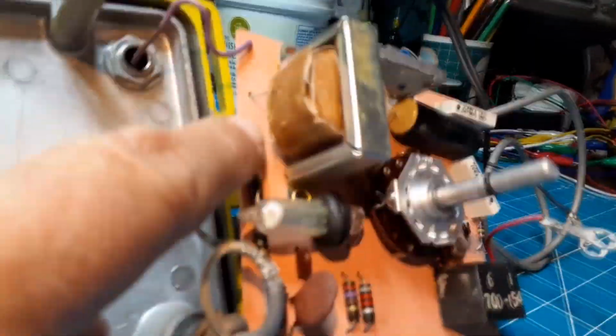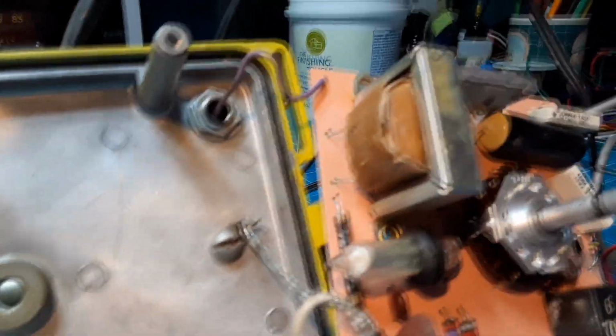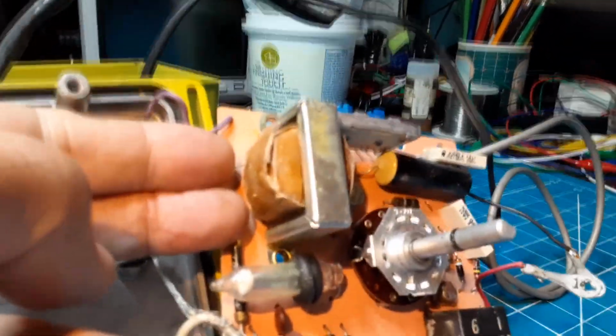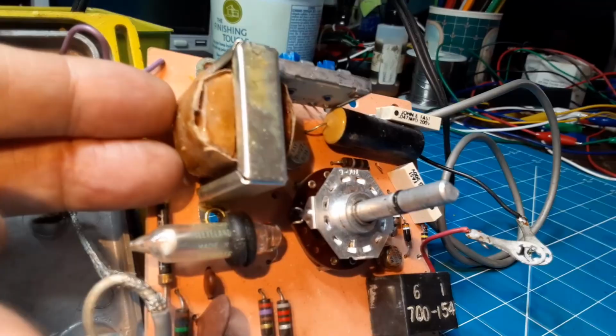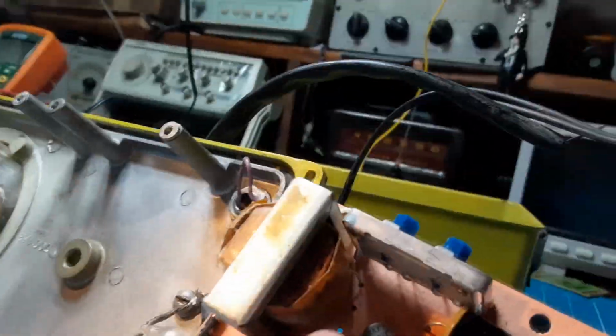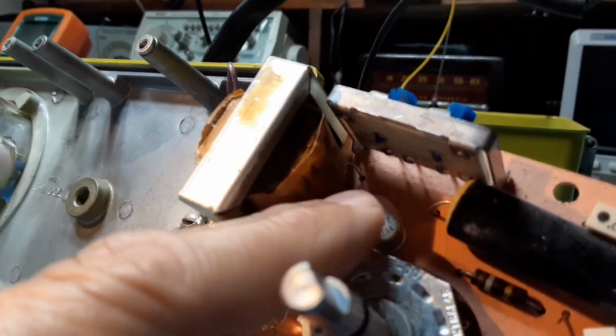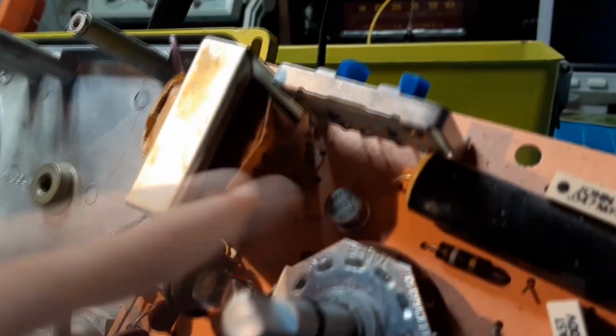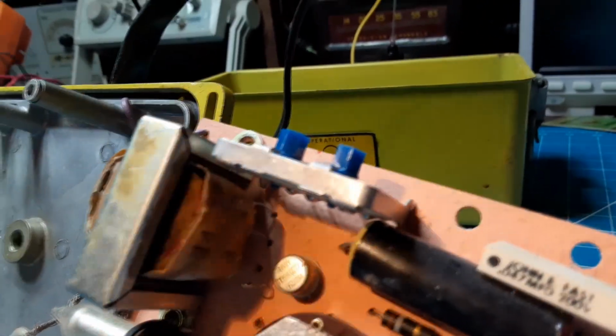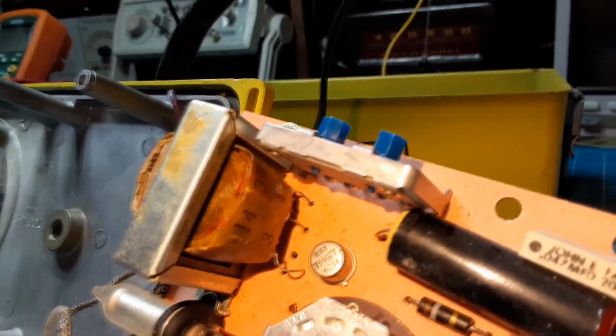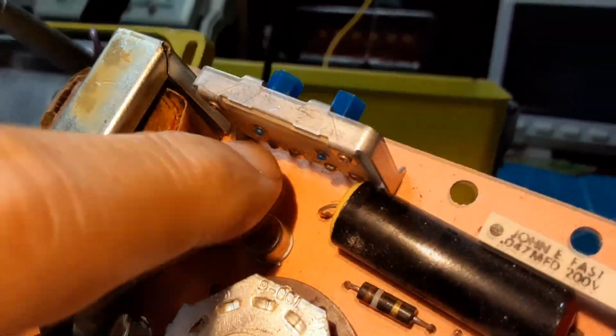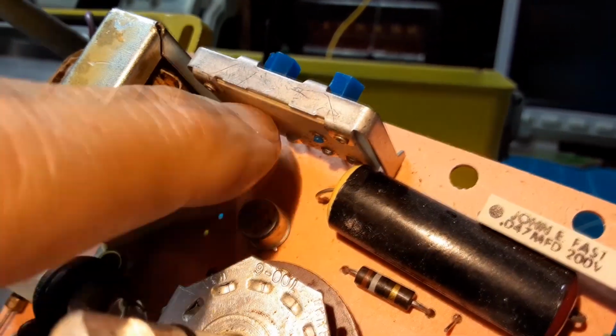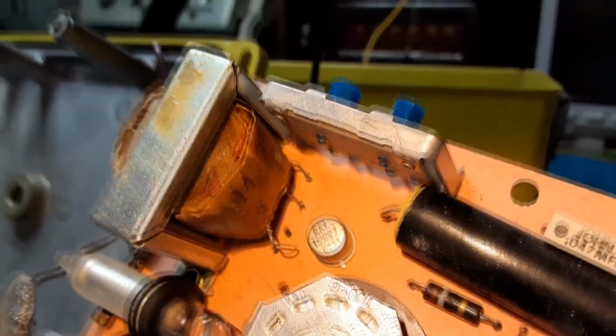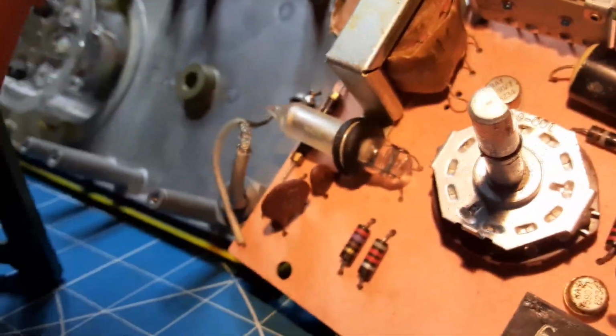So what I did is I lifted one end. Well, first I checked the input side of the transformer here for continuity. And sure enough, there's continuity. It's low resistance. So then what I did is I lifted one lead here. So I wanted to take it out of circuit because when I checked it, let me pull a light over here, I checked across there and I was getting bad resistance. I was getting good resistance from here to here, but I was getting bad resistance. Let me see. I'll show you what we got going on here.